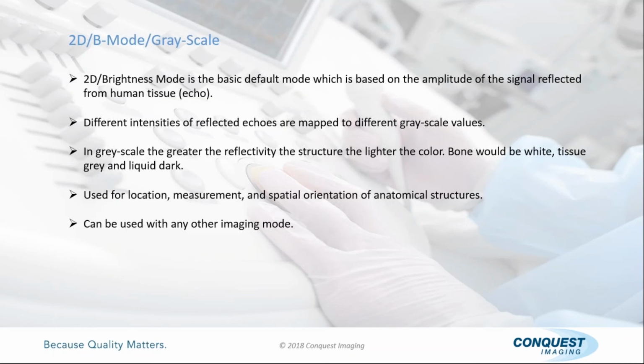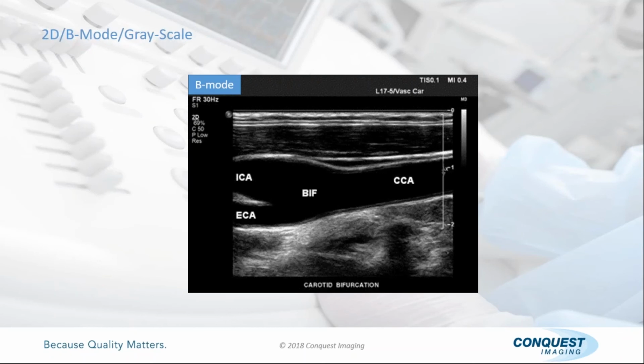I say imaging mode, be careful with that, because there's a mode in ultrasound called continuous wave Doppler, and continuous wave Doppler is not an imaging mode. So 2D won't be used with it, because 2D is an imaging mode. So when they're saying this, here you'll have color. If I changed into color right now, it would still have the 2D image up there. They would just overlay color on top of the 2D black and white, or grayscale, image. Okay? So you're not changing anything. It's being used with color.